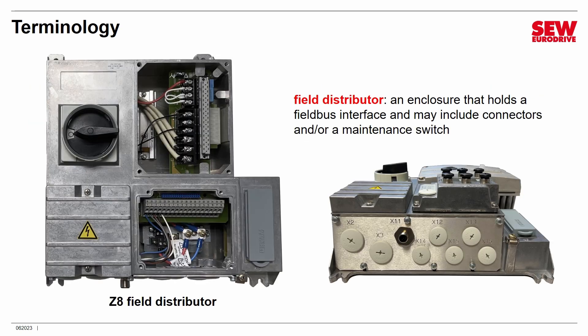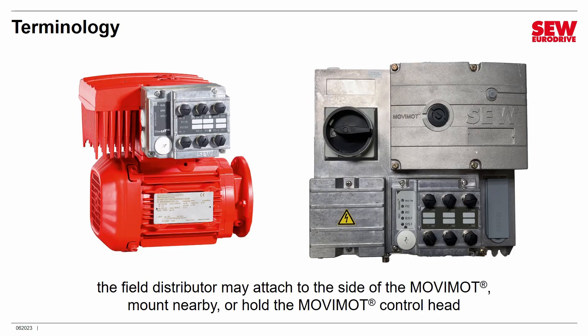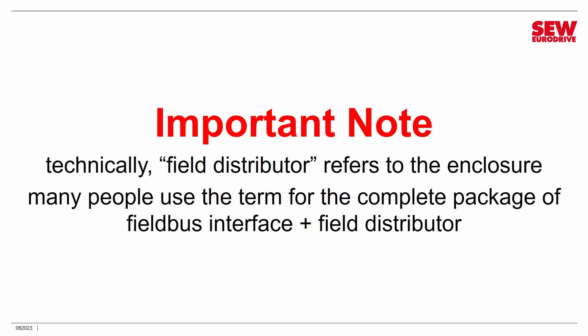Another term is field distributor. A field distributor is an enclosure that holds a field bus interface and may include connectors and/or a maintenance switch. This example is a model Z8 — you can see the connector in the lower right corner and the maintenance switch in the upper left. A field distributor may attach directly to the side of the MOVIMOT, mount near it, or hold the MOVIMOT's control head within it. Note that technically the term field distributor refers just to the enclosure, but many people use it for the complete package — the field bus interface plus the enclosure — and that's how I'll use it throughout this class.